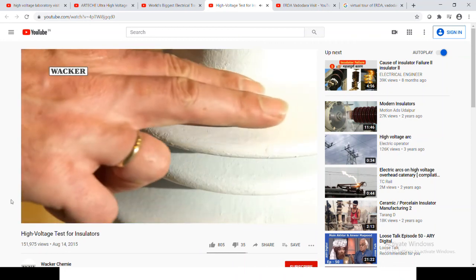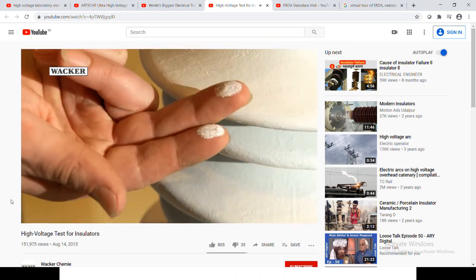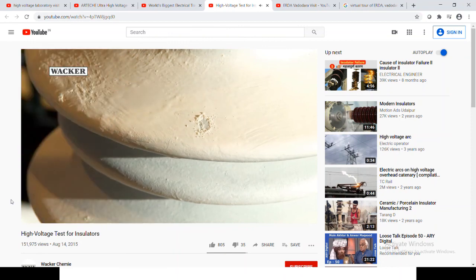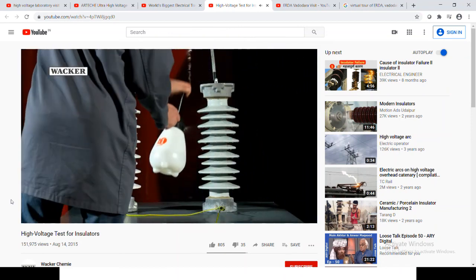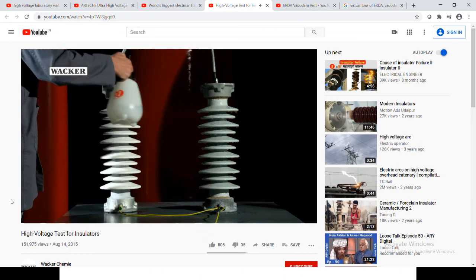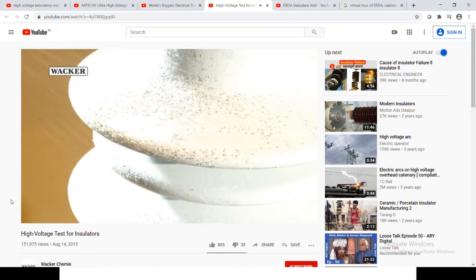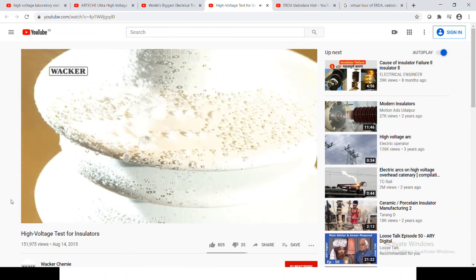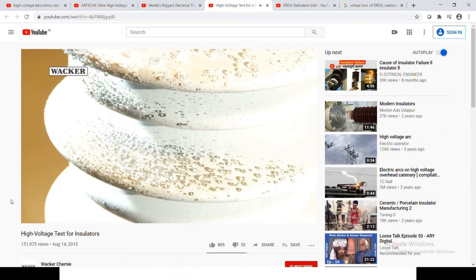In order to simulate realistic environmental field conditions, an artificial pollution layer, which on an uncoated insulator would lead to a pollution flashover under real conditions, is applied to a coated insulator. Both the artificially contaminated coated insulator and the clean uncoated insulator are moistened with saltwater spray. Here, the silicone coating reveals its most important property, hydrophobicity transfer. The silicone's hydrophobic properties are imparted to the pollution layer.